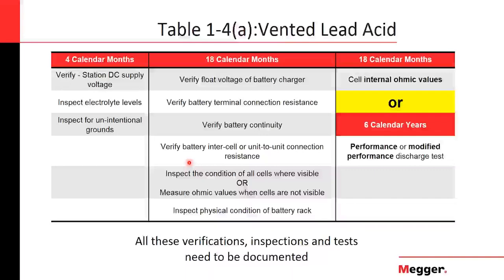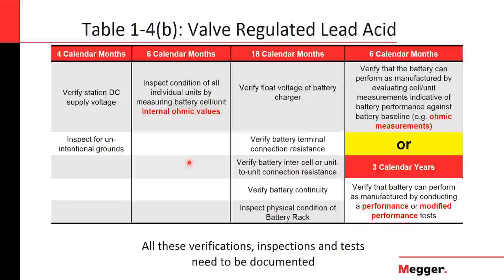This is something that you need to define when preparing your maintenance program. And once you decide what you are doing, you need to keep doing it. I don't have details on what happens if you want to change the method, but you need to keep documentation of all of these tests for the audits. And this discharge test can be done every 6 calendar years. So you can do internal ohmic values every 18 calendar months, or a discharge test every 6 calendar years.